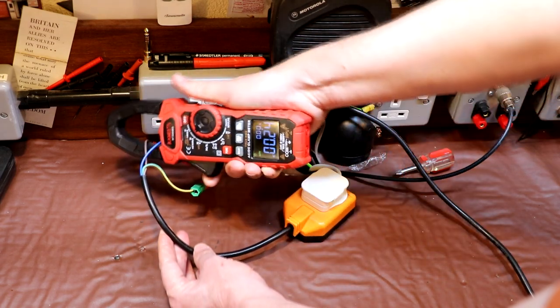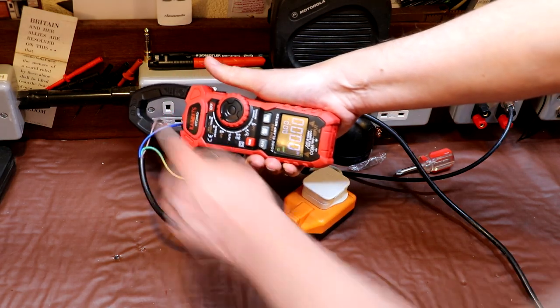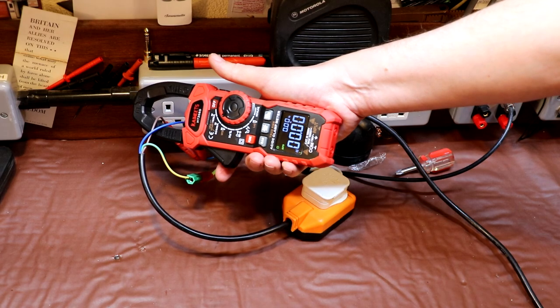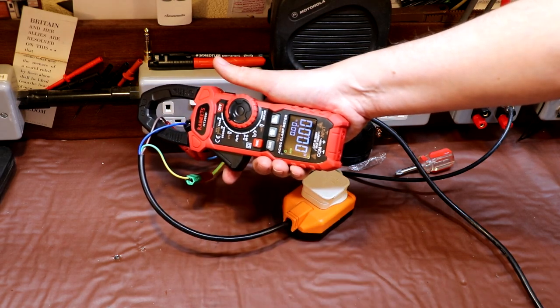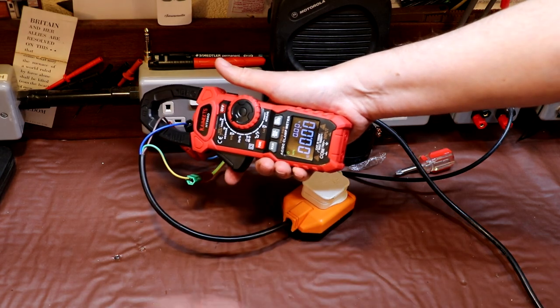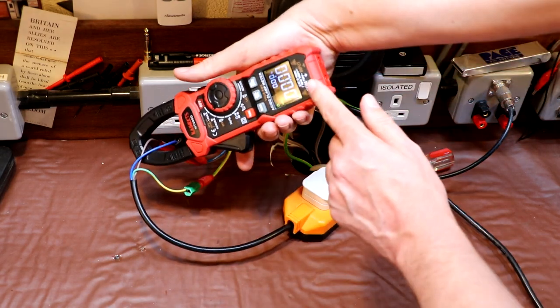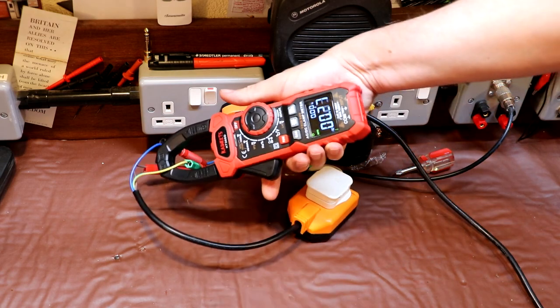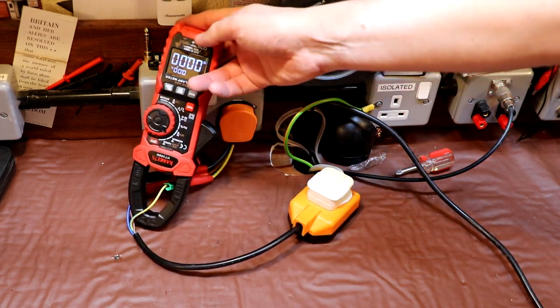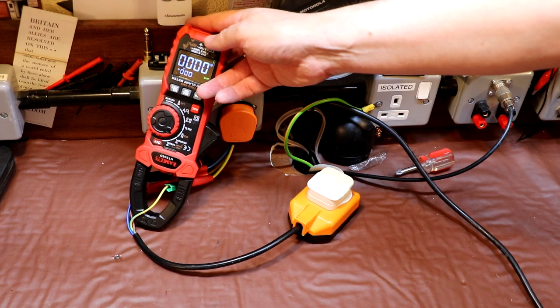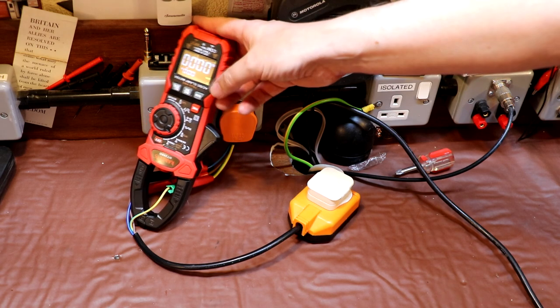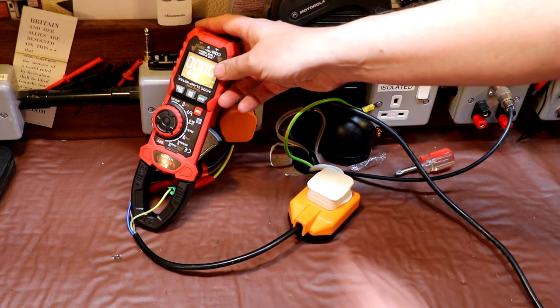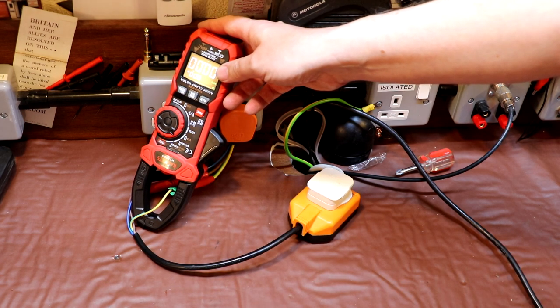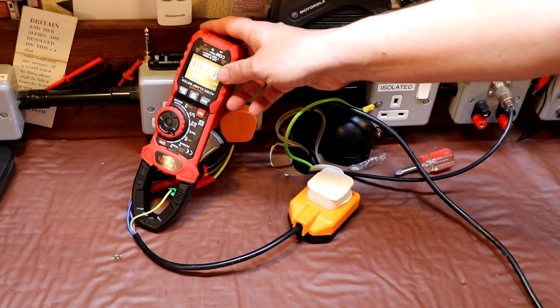Now, if you put your clamp meter across both wires here, the live and the neutral, you should get 0 on the meter, because in theory you'll have no imbalance between the current going into your equipment and the current coming out again. We can also just clip onto the earth, and again we can see that the reading is 0, but I don't quite trust the reading we're getting here, because as we saw, this meter at very low currents does lack some resolution. It's not sensitive to these very low leakage currents, but I do have another clamp meter that is designed for that particular purpose, so let's take a look.